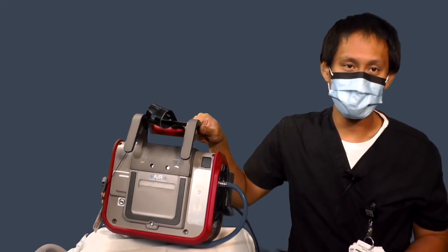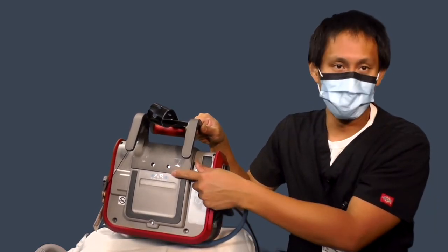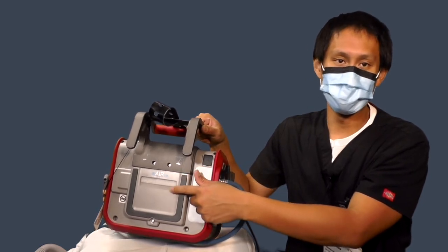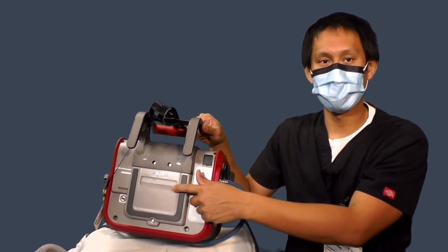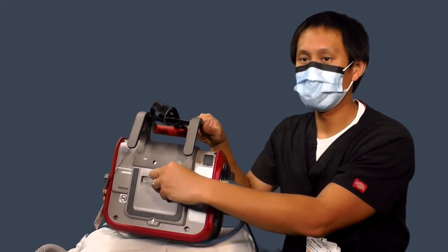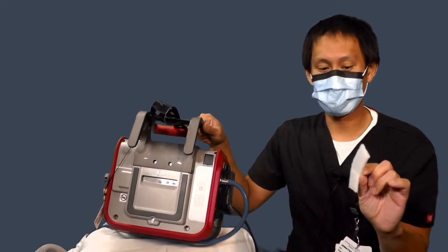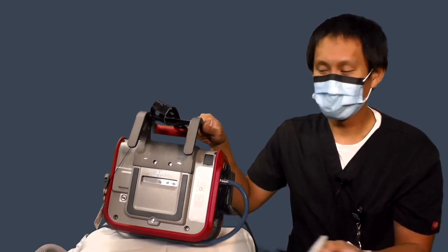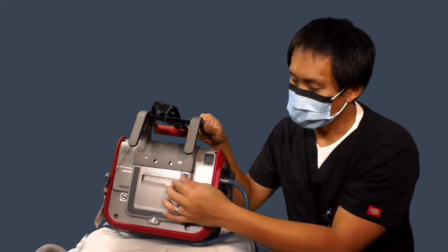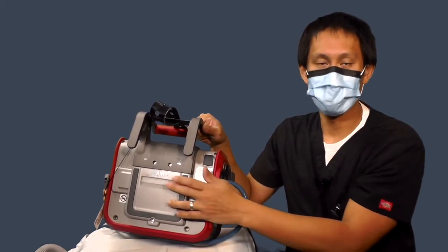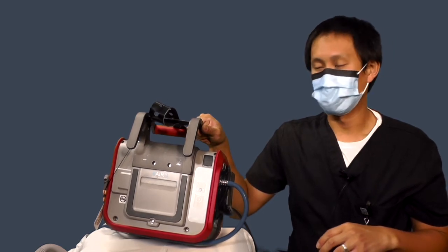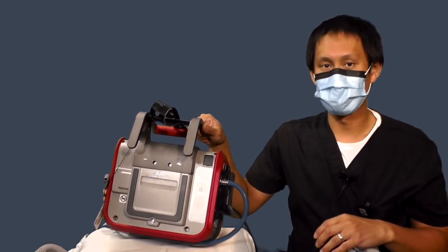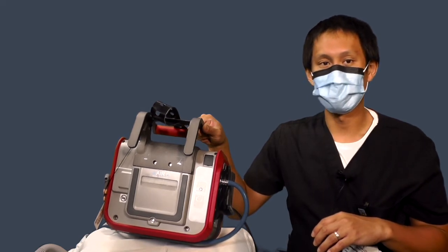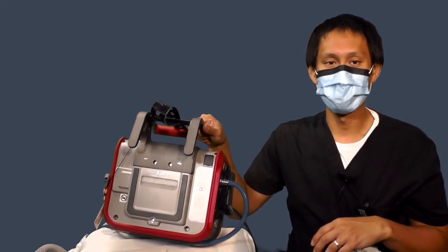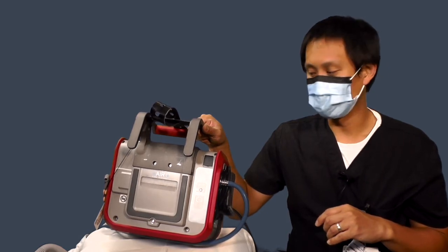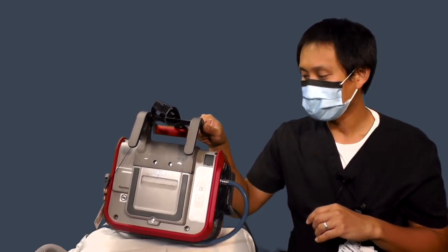Where it entrains the room air is through this air inlet labeled air. You'll notice it's got a removable filter right here. If it does get visibly soiled and dirty, you may try to clean it out or replace it. It just goes in that little slot in there to replace. Okay, these air filters do not need to be replaced every single time you use it. You can replace it when it's visibly soiled or during the routine PM on the vent itself.